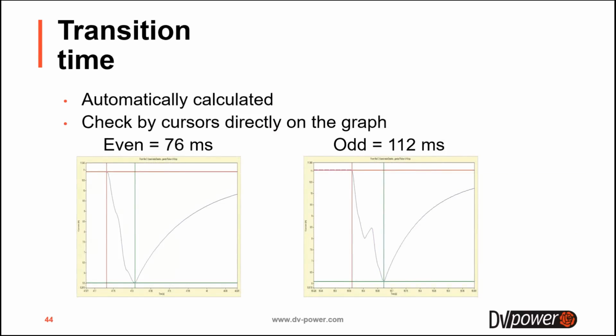So we mentioned that transition time can be automatically calculated by the software, but of course it can also be checked manually on the graph using the cursors. You can see here an example where in even tap positions, in even transitions, the transition time was 76 milliseconds. In odd transitions, it was prolonged to 112 milliseconds.